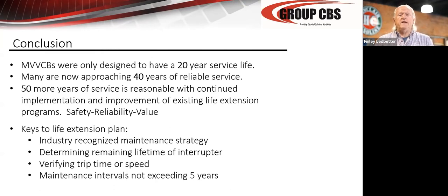Determine the remaining life of your interrupters and your breakers and your switchgear, and put together a capital plan to upgrade what you can. You know, the relaying, the CTs, the PTs, insulating material. If you've got stuff built in the 80s, you've got a lot of hygroscopic stuff in there that'll absorb moisture. Get the bus bracing out and the bus tubing out that is organic. Get that stuff out of your switchgear or you're going to get bit by it.